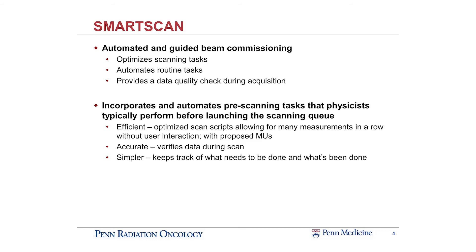The Smart Scan software component really automates and guides the user in the whole scanning process. It will optimize your scanning queues, it automates some routine tasks that we typically have to do in the beginning — background, CAX check, prelim scans — and also provides a data quality check that's routinely done during the scanning acquisition, so it constantly is looking at your data and telling you whether your data is good or not. It's really an efficient tool that incorporates and automates all your pre-scanning tasks that we physicists like to perform before launching your scanning queue.